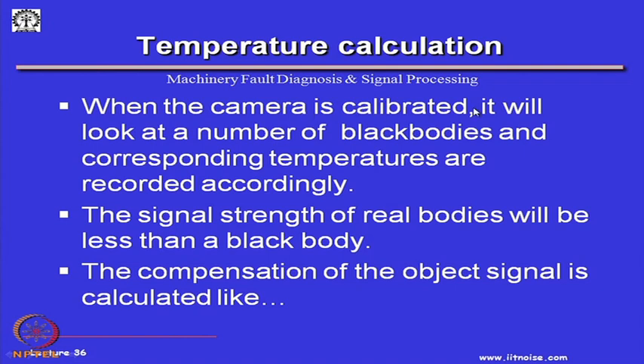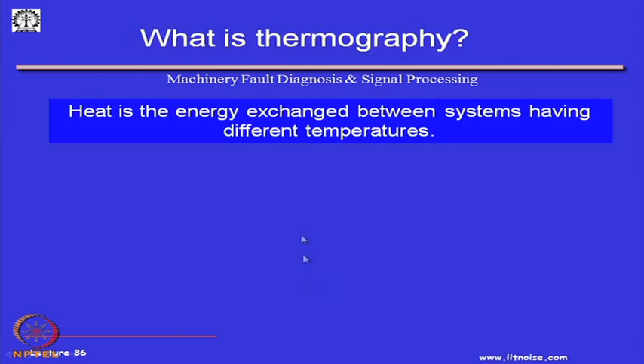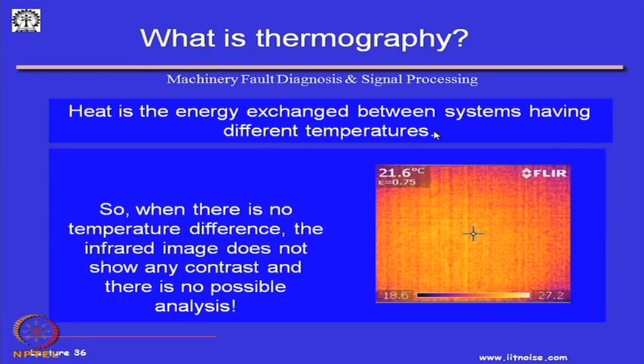So, when the camera is calibrated, it will look at a number of black bodies and record corresponding temperatures accordingly. The signal strength of real bodies will be less than a black body. The compensation of the signal is calculated like this: heat is the energy exchange between systems having different temperatures.